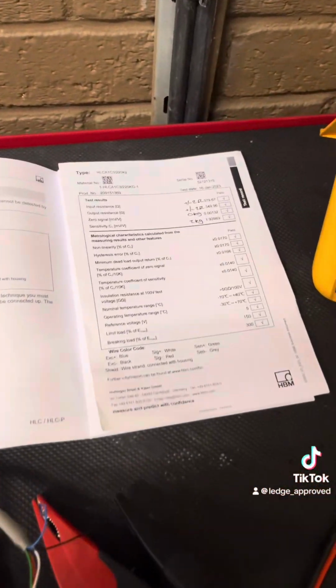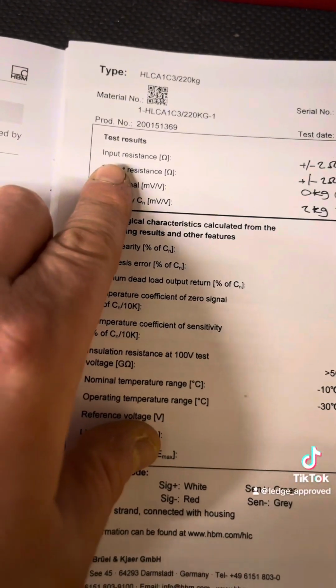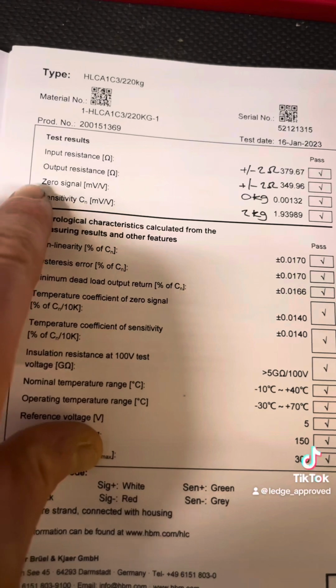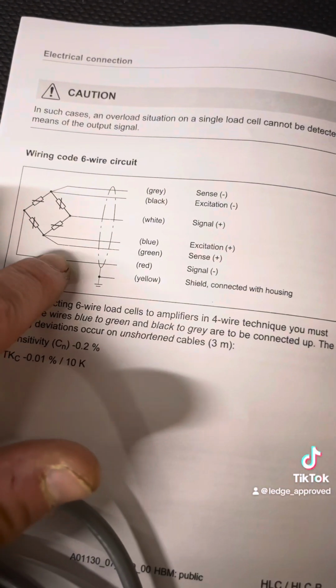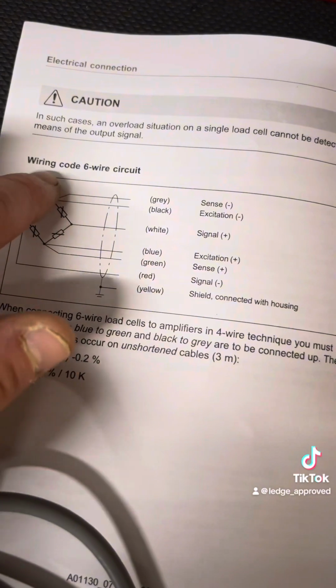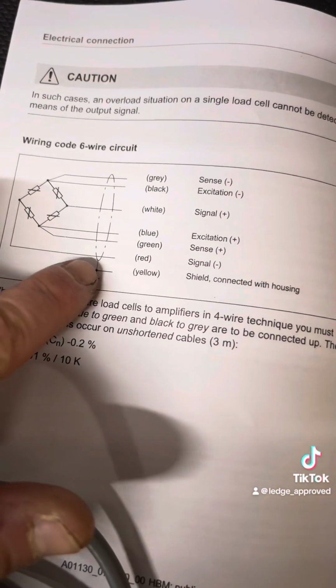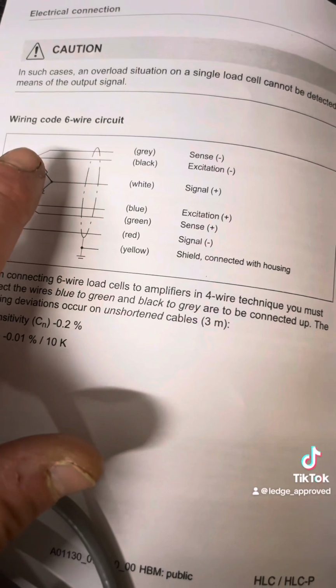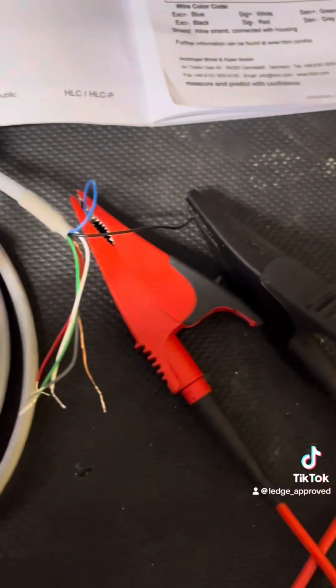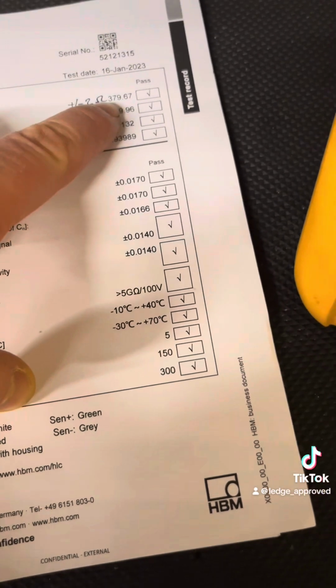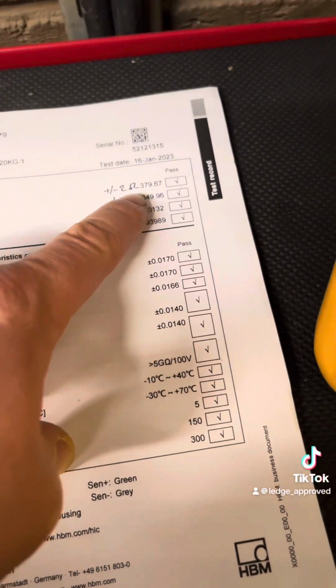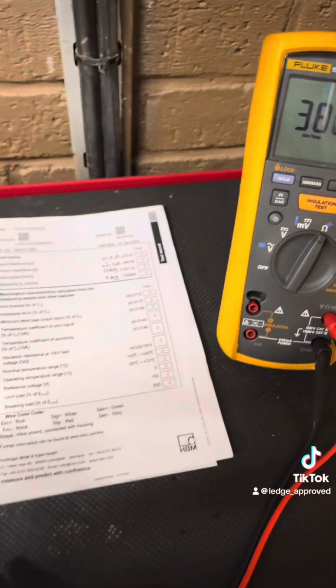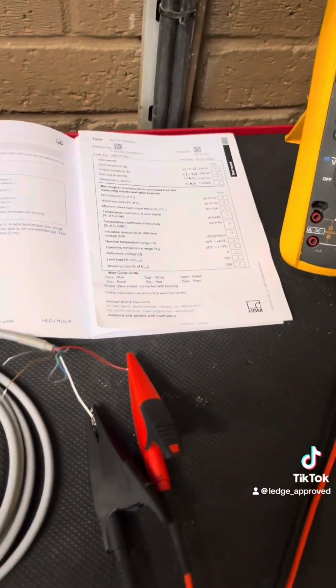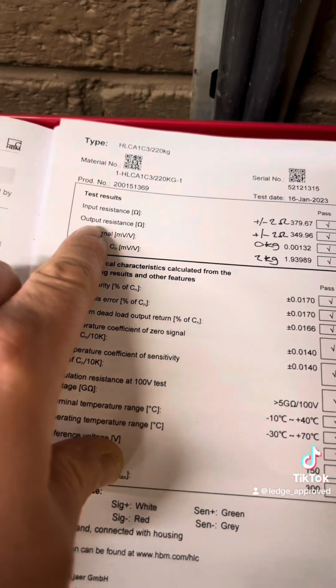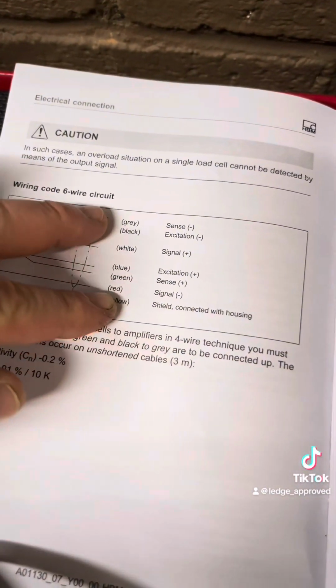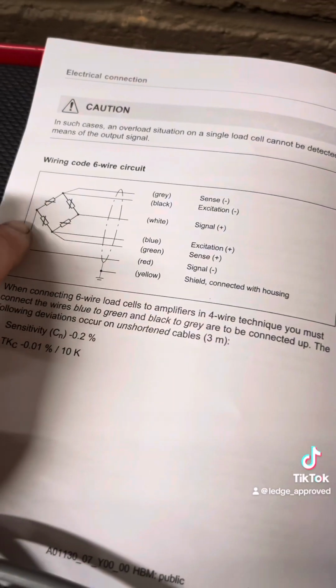So the second one is really easy again. What we want to do is with it off the machine and disconnected, we want to check our input resistance and our output resistance. So with the meter on ohms, all we're going to be doing is checking the resistance, but we want to be within about 1 or 2 ohms plus or minus. I believe it's 2 ohms. Yeah, 2 ohms plus or minus of what the calibration sheet's showing. And we're pretty much good on this one. And then just do the same again on your output. Crocodile clips across your plus and minus, and again 2 ohms.